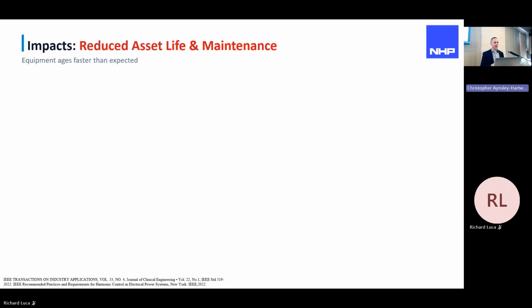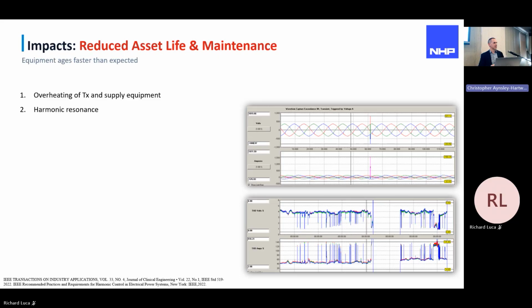The next set of impacts fall under reduced asset life and maintenance. So it's where the equipment ages faster than expected. And we've already spoken about overheating of the transformer and supply equipment. But harmonic resonance is a real thing. If you've read any books about it, the physics book talks about the wine glass experiment with the opera singer. You heard about that one? Everything in life resonates, so it has a resonant frequency. If we look at a wine glass, its resonant frequency is just over 500 hertz, which means at that frequency, if someone can raise their voice that high, they'll end up shattering the glass. That glass will absorb all the energy at that particular frequency. Its atoms start to vibrate and it will shatter.